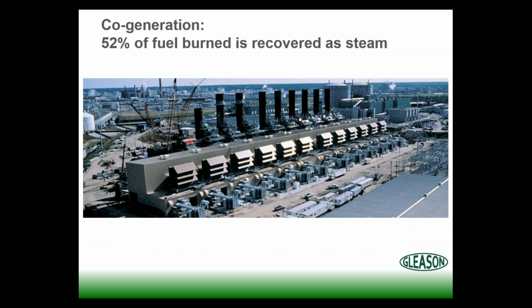Big term in the industry: cogeneration, or if you're really talking the lingo, it's CHP, combined heat and power. And another beauty of steam is we can do mechanical work with steam. We can run a turbine, which can turn a generator, and we create electricity. An example of CHP or cogen is we can do just that. We can produce electricity. Then we take that lower pressure steam off the downstream side of the turbine and heat the building with it, or make chicken soup, or make tires, whatever it happens to be. We're simply improving the overall thermal cycle efficiency of the system.